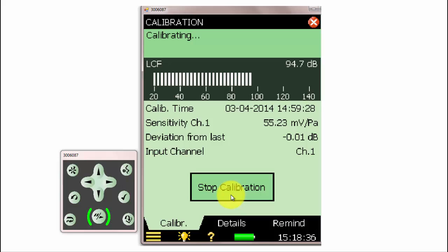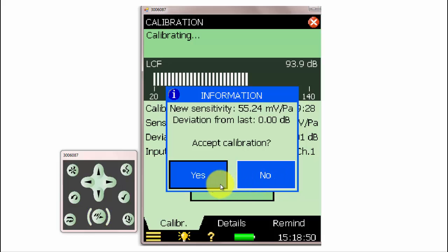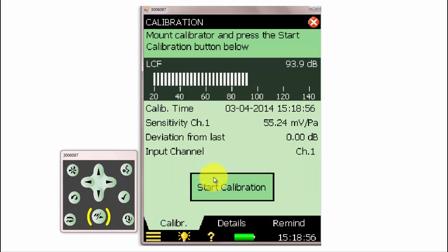The meter will make a measurement of the calibration tone and compare it to the last calibration value. We can select to either Accept the new calibration value or Reject it. When we select Yes, a record of the calibration will be saved on the meter and the calibration will be applied.